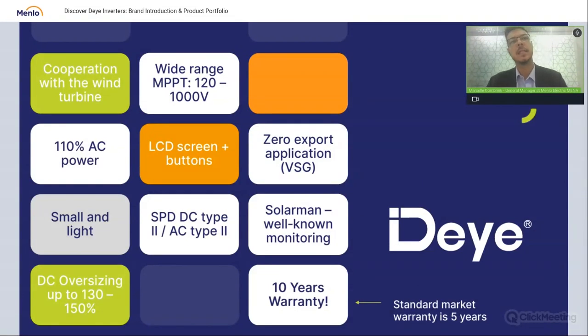DC oversizing, depending on temperatures, can be anything between 130 to 150%. Also be mindful that when you do your DC oversizing, please just give us a call to make sure that it is acceptable. If we need to get special approval from Deye, we can do that and ask them to support us on that, but that would also depend on where your location is, temperatures, and all of those relevant input scenarios.